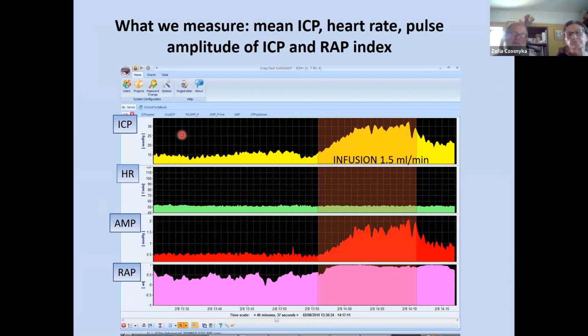We measure baseline pressure. When we start infusion, this grayish area, we observe an increase in intracranial pressure. We usually use infusion of 1.5 mL per minute, sometimes 1 mL per minute when baseline pressure is increased. Then we measure heart rate. This is for us a good indicator that pulse amplitude is easily detected by the computer. Then pulse amplitude, which is increasing proportionally to infusion, to intracranial pressure, you see.